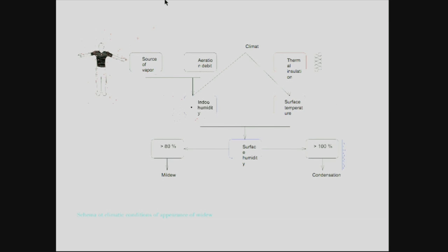When we breathe, we lose a lot of water into the air. And so after one moment, depending on the number of people in the room and the size of the volume of the room, you reach the saturation curve. It means that the air at a certain temperature can no longer accept more water, and so it creates condensation, and for the building it could also create some mushrooms or other problems for the construction.